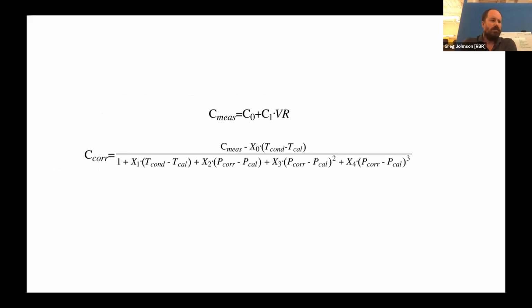Finally, conductivity. So conductivity is an interesting one because we use the inductive principle of measurement rather than a contact or electrode measurement technique. The way that this works is that we have inside this cell two ferrites arranged one above the other, and they cannot see each other electrically. We take a coil and wrap it around one of the ferrites, and by exciting that coil with an AC waveform, we're able to induce a current that passes through any conductor that's running through the center of that ferrite.